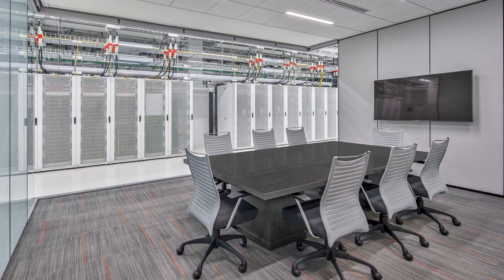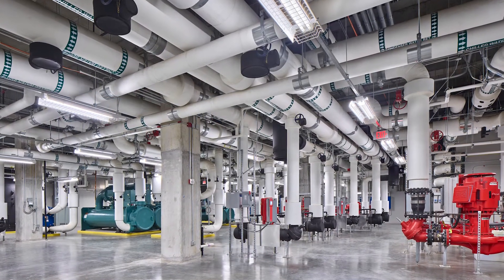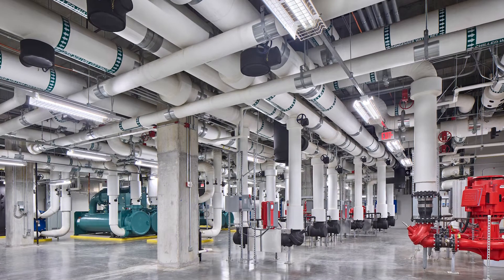The three different types of cooling that we've got in this facility are liquid cooling to the cabinet, which provides an ultra-low PUE and an ultra-high density per cabinet. So you can do things like HPC with university research here, up to 100 kilowatts per cabinet, no problem, at a PUE of about 1.15.